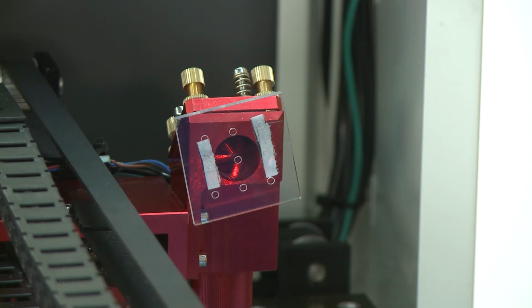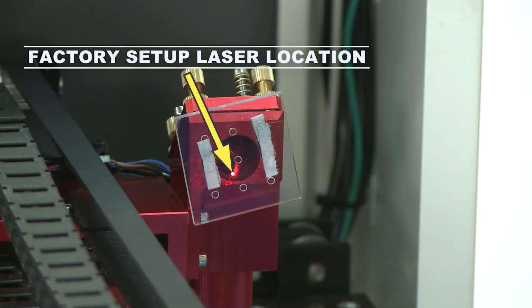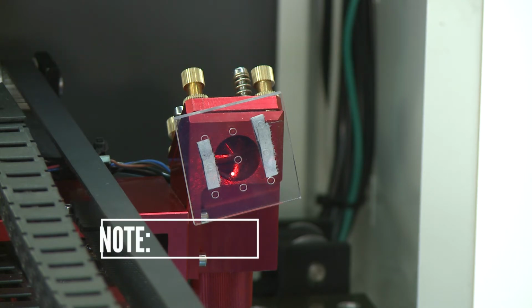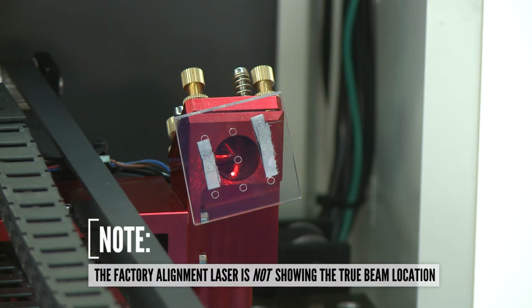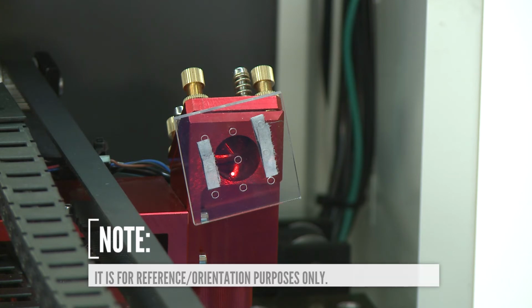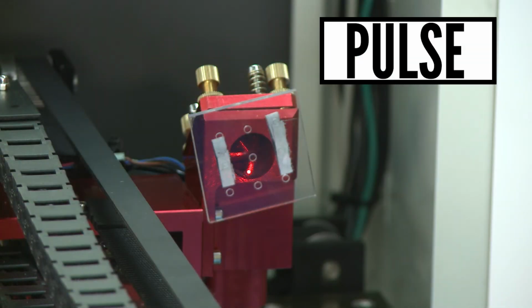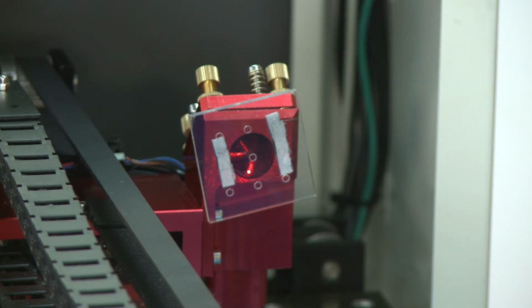When we're ready to pulse the laser beam and check the alignment of the actual laser, this is where we can use the factory alignment laser as a useful tool. We use it purely as a reference. If we shoot the laser beam and it shows that it's in the upper right-hand quadrant, we know we can move the reference laser down into the left to better align the actual laser. You can use the pulse function on the laser head to make a mark on the Lexan where the actual laser beam ends up.